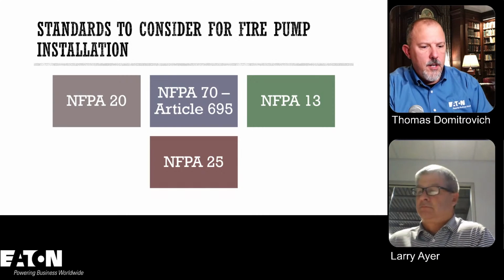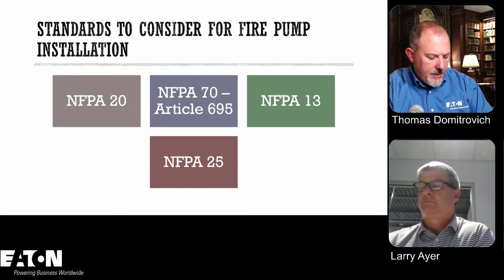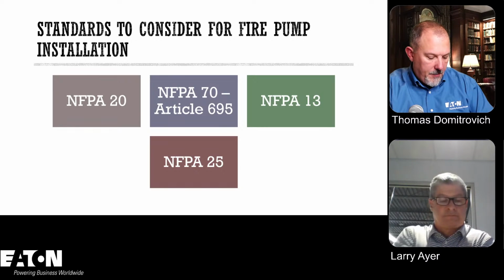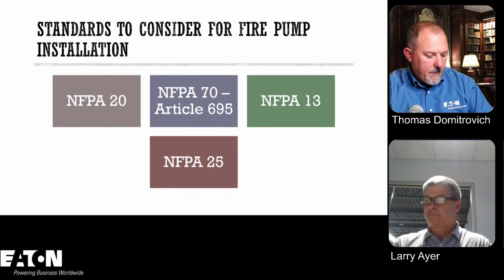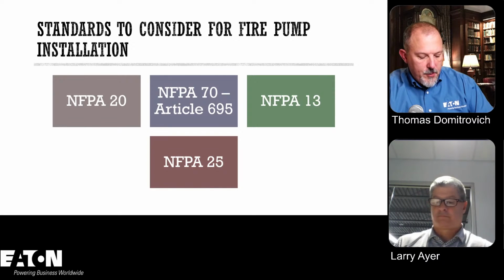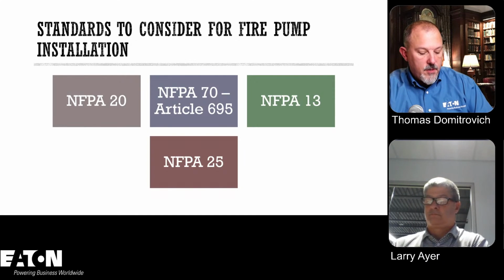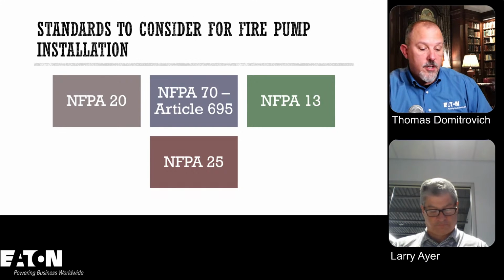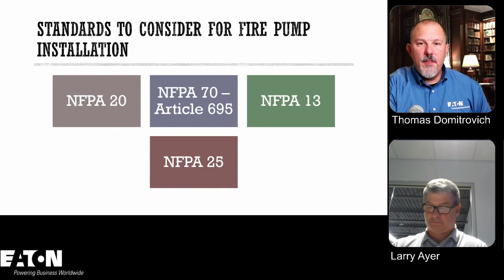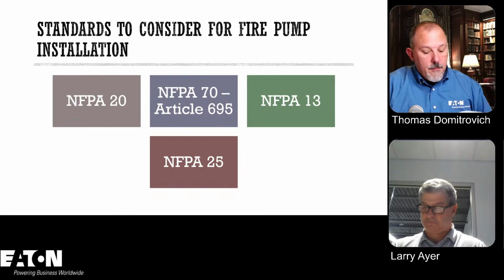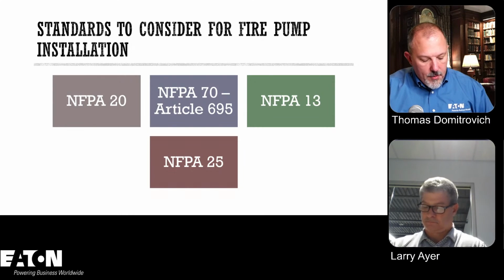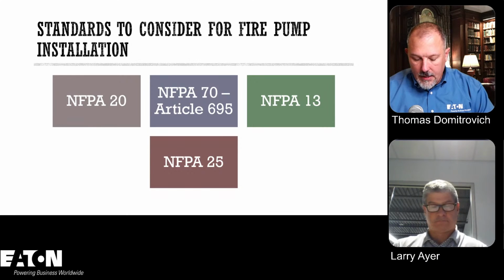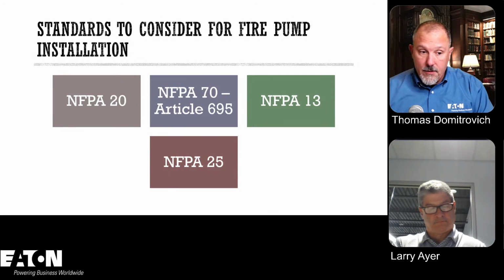Yep. And then, Al Teresi noted that 110.28, which talks about enclosure types, says that portable power distribution equipment, termination boxes, general purpose transformers, fire pump controllers, fire pump motors, motor controllers rated not over 1,000 volts nominal intended for such locations shall be marked with an enclosure type. So the National Electrical Code tells you to mark the enclosure type, but I can't find anything in the NEC that says it has to be a minimum of a NEMA type 2, unless somebody out there knows better than I do.